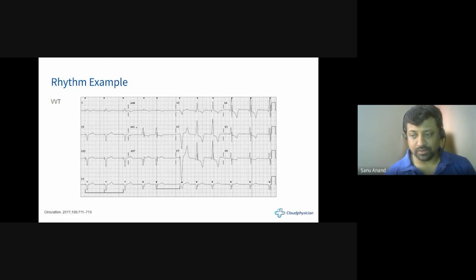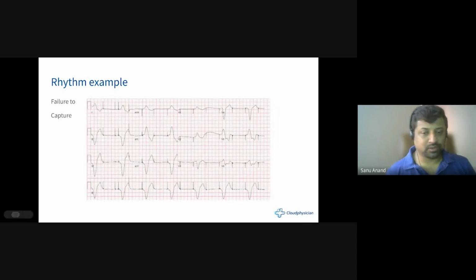And here, this refractory period is what I mentioned earlier. This particular impulse has fallen on the absolute refractory period of the ventricle. Maybe this is a little complex, but it's fine if some of you do not follow it. Don't fret over it. If it falls on the absolute refractory period, that's the reason it's not triggering. So in this particular case, they reconfigured it to VVI, and it was fine after that.